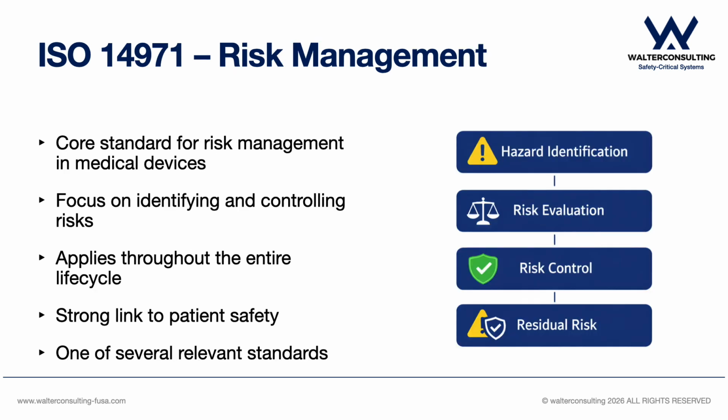Let's start with ISO 14971. This standard focuses on risk management. It defines how hazards are identified, how risks are evaluated, and how they are controlled. But here is the key question. What is the main goal of all of this? The answer is simple: patient safety.